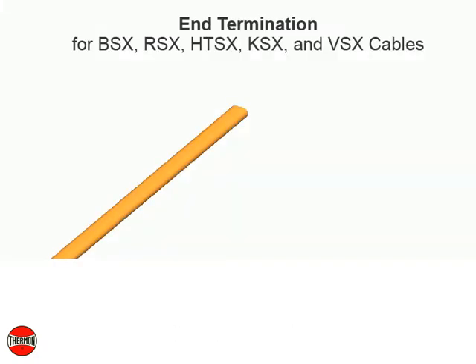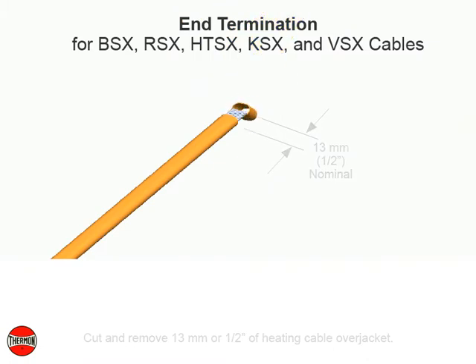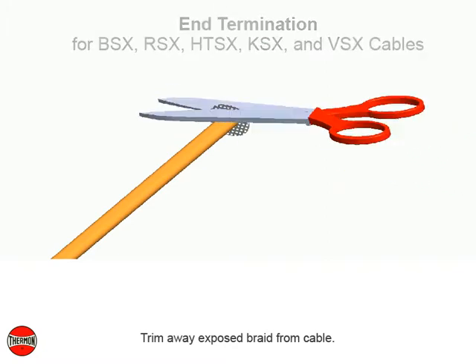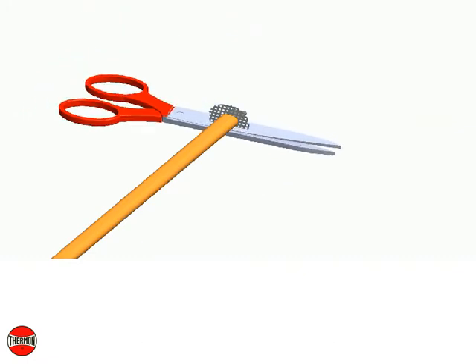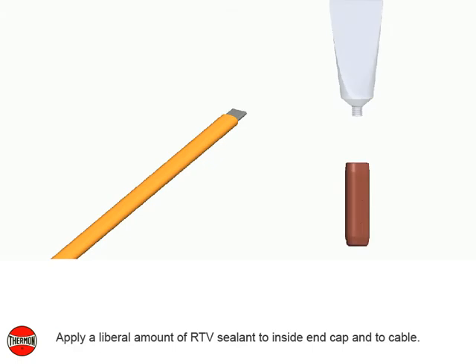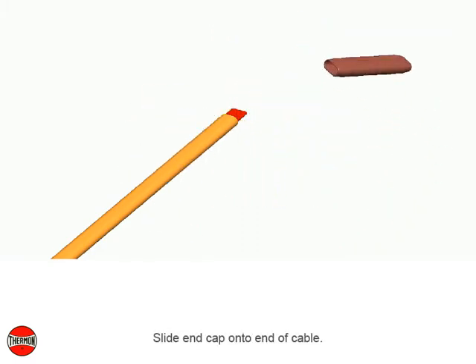End termination for BSX, RSX, HTSX, KSX, and VSX cables. Cut and remove 13 millimeters or 1/2 inch of heating cable over jacket. Trim away exposed braid from cable. Apply a liberal amount of RTV sealant to inside of end cap and to cable. Slide end cap onto end of cable.